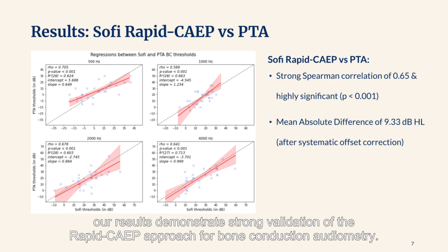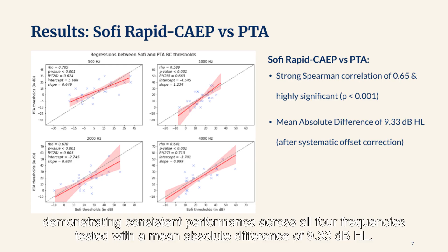After applying the systematic offset correction, our results demonstrate strong validation of the rapid CAEP approach for bone conduction audiometry. We achieved a strong Spearman correlation between Sofi with rapid CAEP and PTA with a correlation coefficient of 0.65, highly significant at less than 0.001. These correlation plots show the results after systematic offset correction, demonstrating consistent performance across all 4 frequencies tested with a mean absolute difference of 9.33 dB HL.